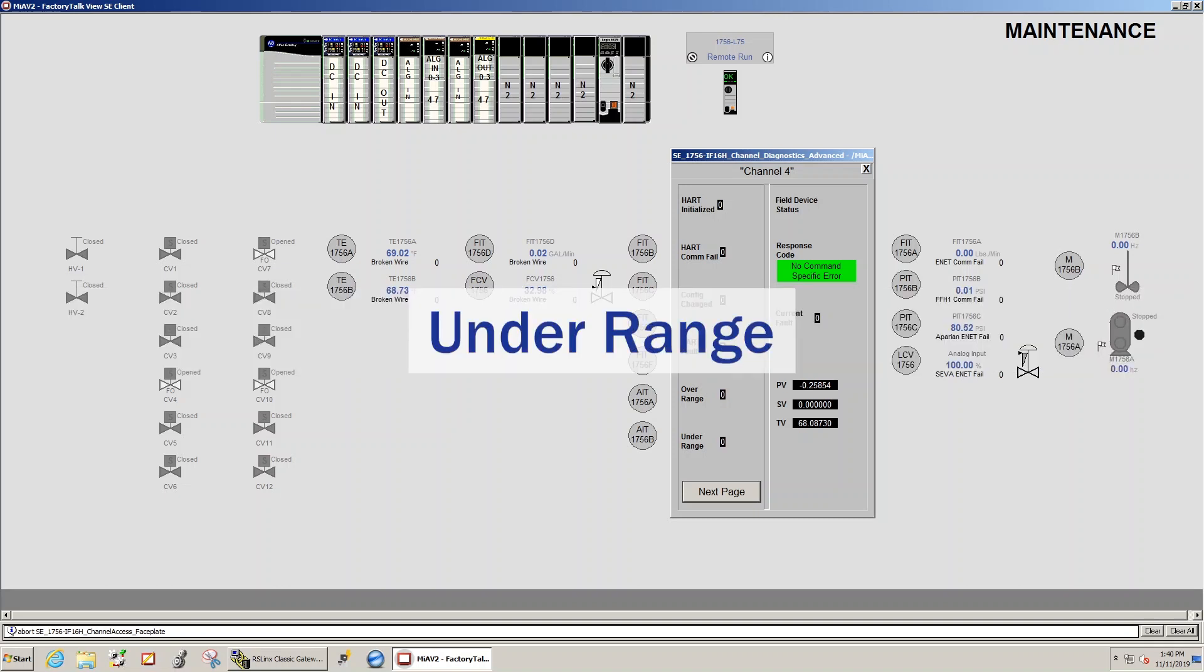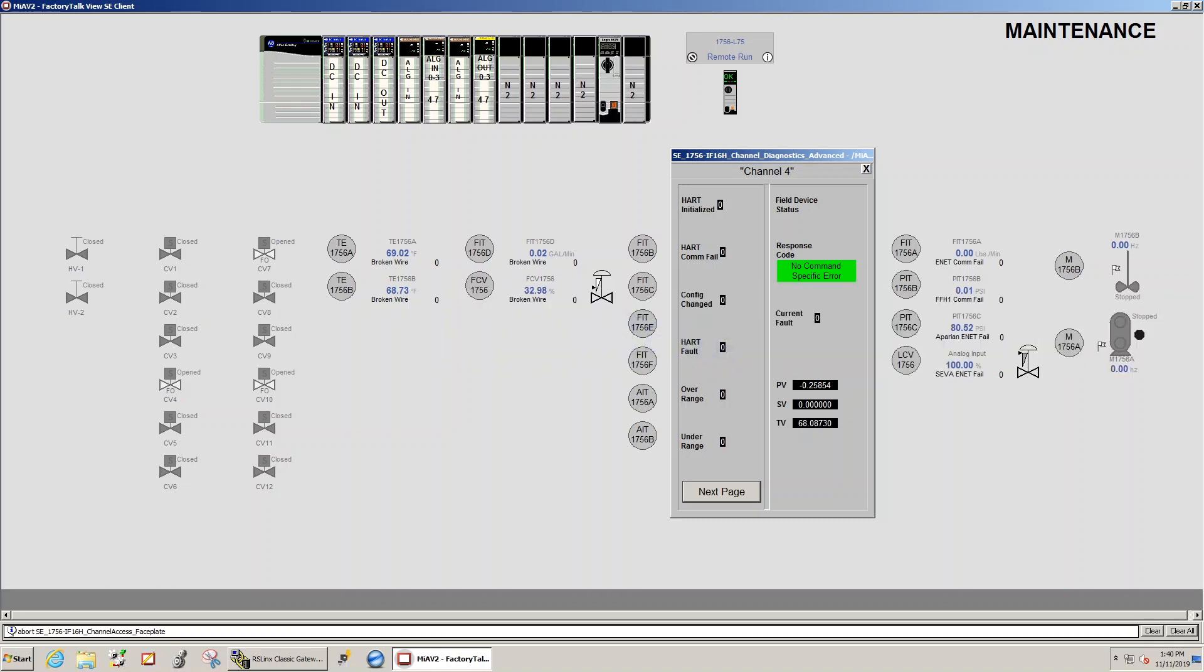This bit will go high if our milliamp signal is less than 3.4 milliamps if our transmitter is configured for a 4 to 20 milliamp signal.